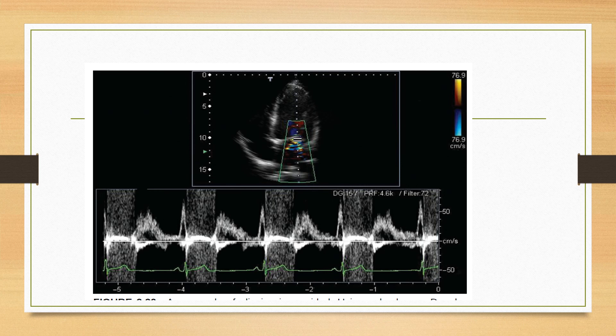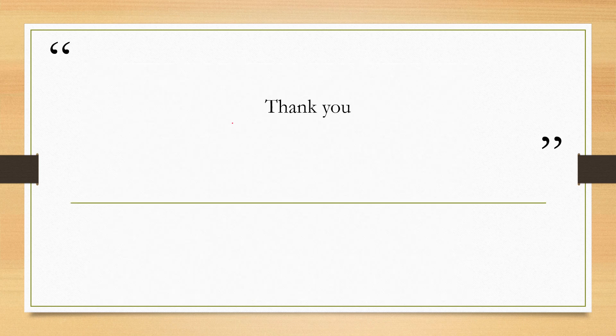Aliasing also occurs in color flow mapping. Even though a jet is moving forward, aliasing can give a false impression that the jet is moving towards the probe, displaying a red color — which actually represents an erroneously false frequency due to the limitation in Pulse Repetition Frequency and the Nyquist Limit. This concludes the basic concepts of Pulse Wave Doppler, aliasing, Pulse Repetition Frequency, and the Nyquist Limit.